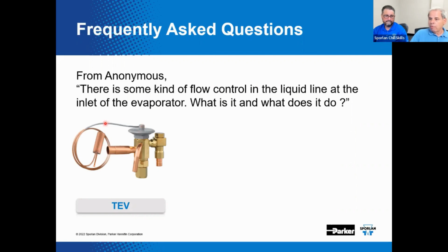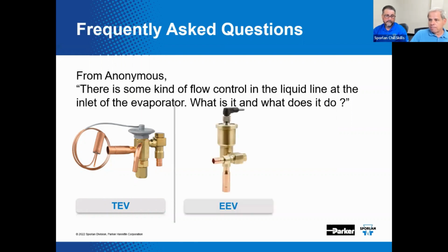Correct. So we've had some folks who have a hard time recognizing this device, and they'll see this copper cap tube and think it's maybe some kind of cable, but it's a conduit for the thermostatic element constituents that are helping to control the valve, tell it what to do so that it can control superheat. It's nothing but a pressure communication device. Right. What else could this be? Well, it could also be an electronic or electric expansion valve. This one we're showing here is an electrically actuated, electronically controlled stepper valve. And this one actually has a cable attached to the motor assembly. I guess that's what you'd see here. That's correct. Compare and contrast that to the copper cap tube over here. Well, the copper cap tube on the TEV, like I said, is just a pressure communication device between the bulb and the diaphragm head on the valve.